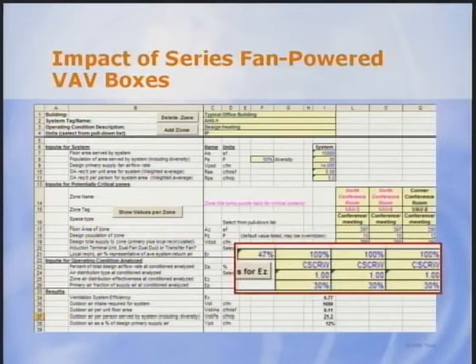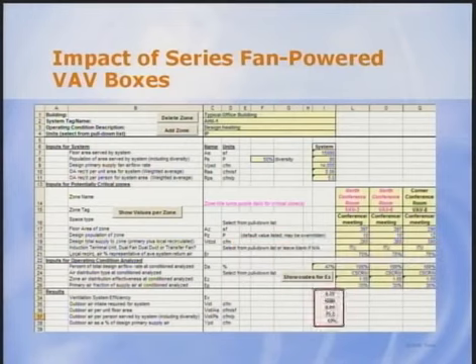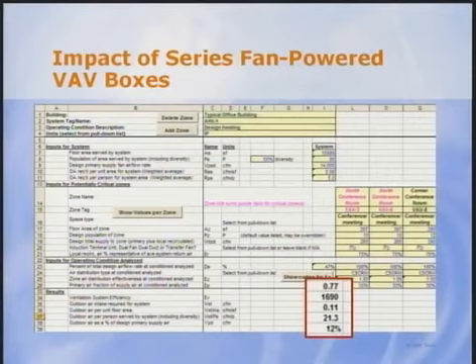We also changed the percent of design airflow rate on line 23 to 100%, since these are series fan-powered boxes. And we changed the ventilation effectiveness code to that corresponding to overhead heating with air less than 15 degrees above the space, which is possible with fan-powered mixing boxes. The critical zones are now the two north conference rooms again, but the system outdoor air rate drops by more than half to 1690 CFM, about the same as that required in the cooling mode.